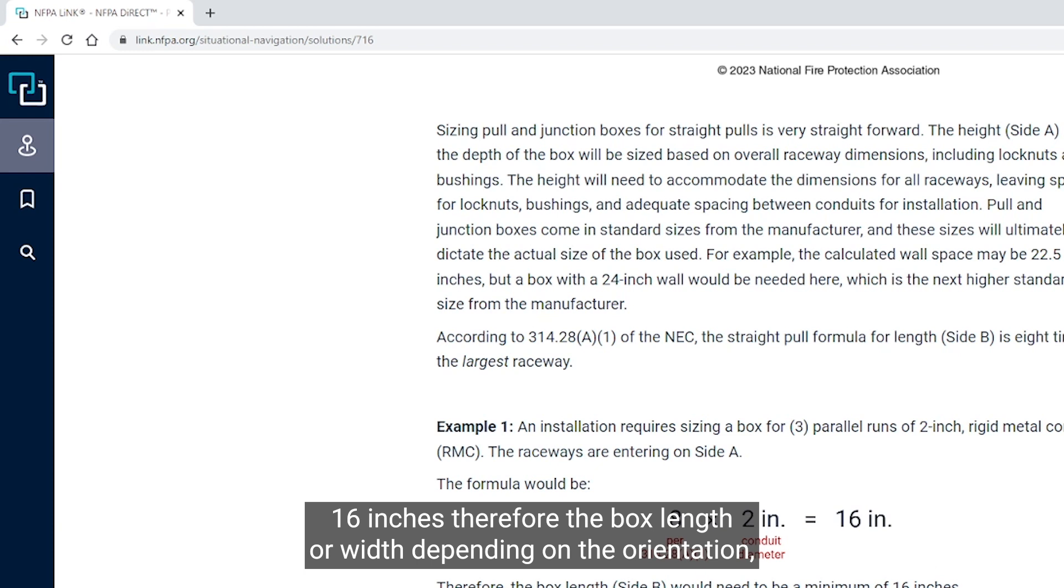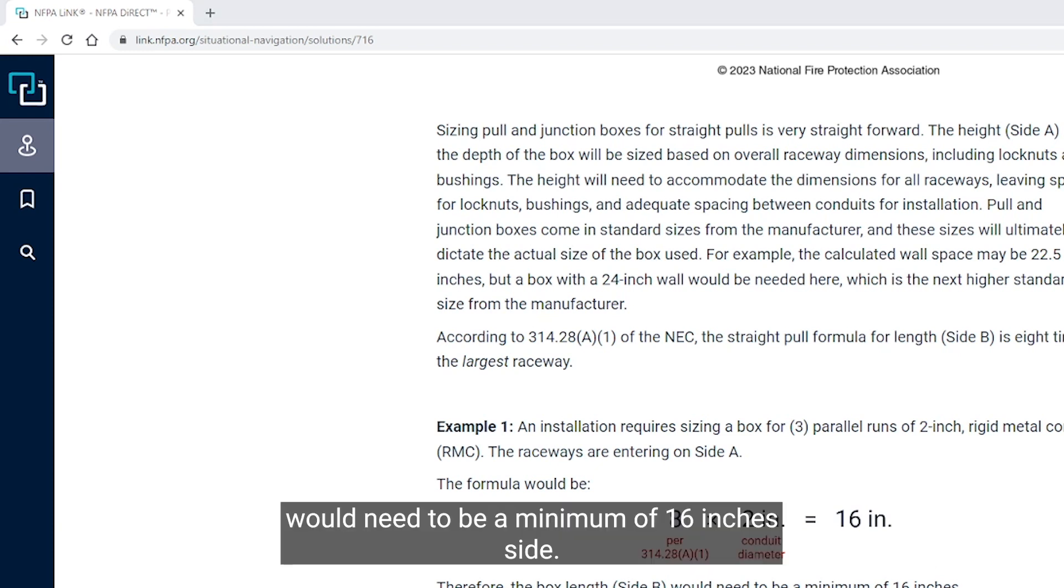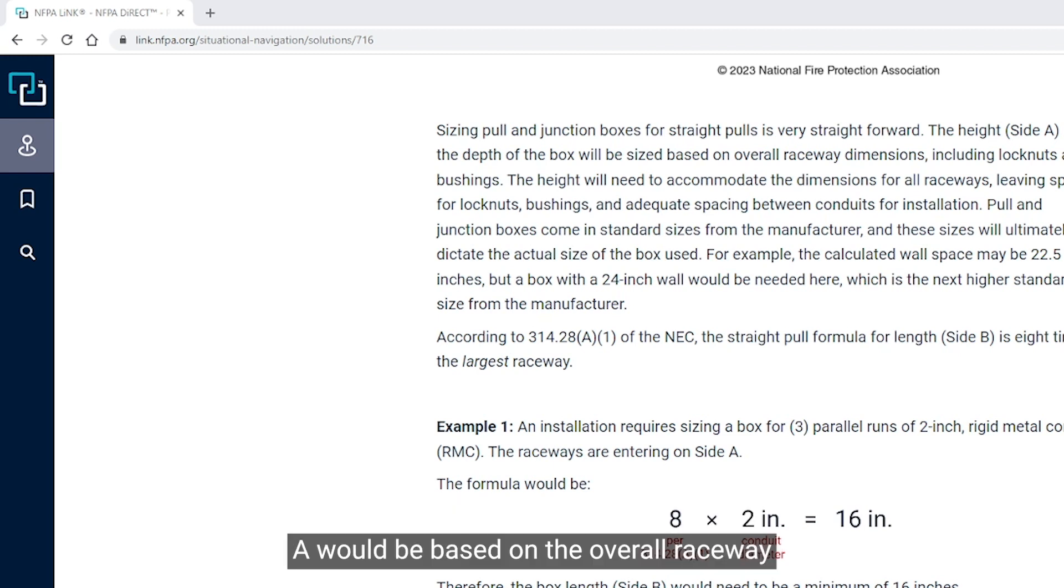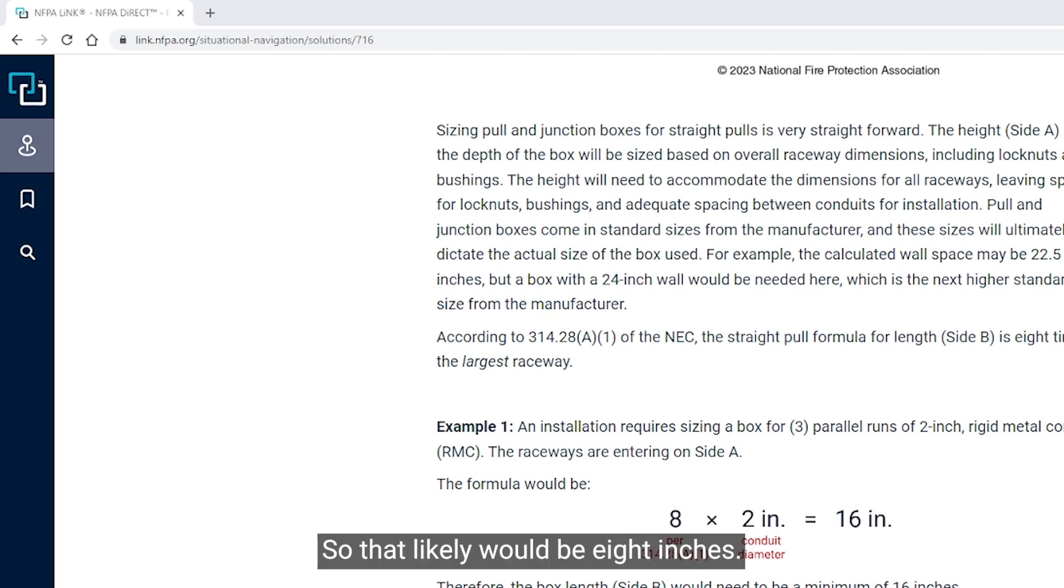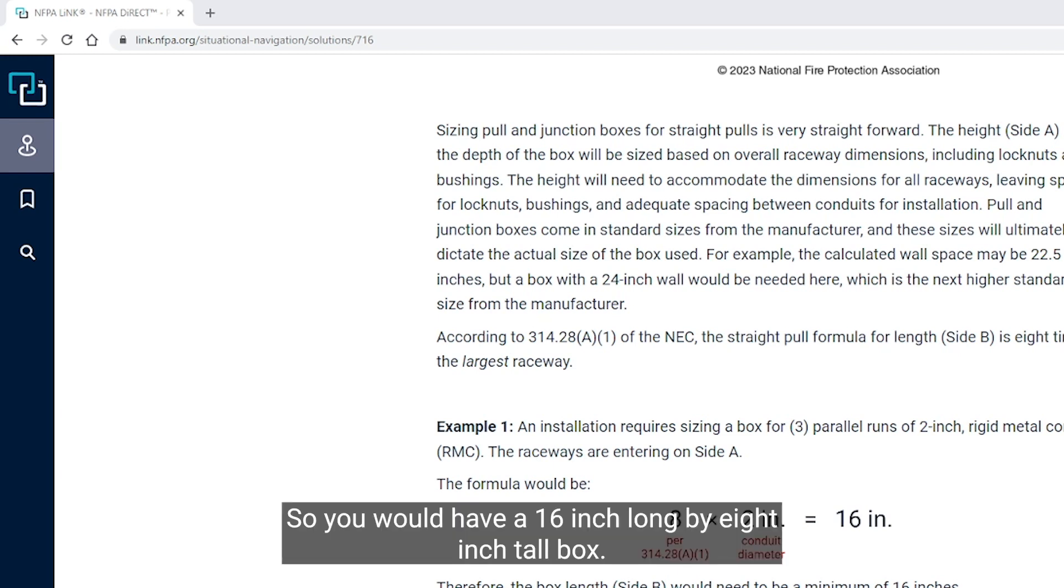So we're solving for B. We have three parallel runs of two-inch rigid metal conduit. The raceways are entering in on side A. So eight times two would equal 16 inches. Therefore, the box length or width, depending on the orientation, would need to be a minimum of 16 inches. Side A would be based on the overall raceway dimensions plus room for lock nuts and bushings, so that likely would be eight inches. You would have a 16-inch long by 8-inch tall box.